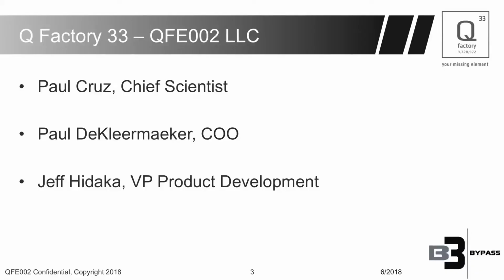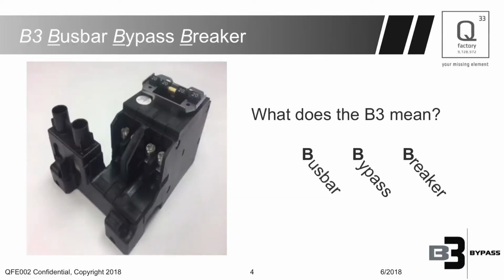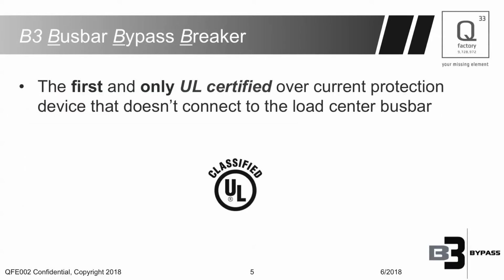Myself, Paul DeKleermaeker. In the back, we have Paul Cruz, who's our principal scientist, and we're very fortunate to have Jeff Hidaka, who is in charge of our development. He spent 32 years at UL and was their principal engineer for breakers. So B3 ByPass, what does it mean? It means Busbar bypass breaker. And what is the significance of this? It is the first and only UL certified overcurrent protection device that does not touch the bus bar of the main panel. And I'll explain why this is important.